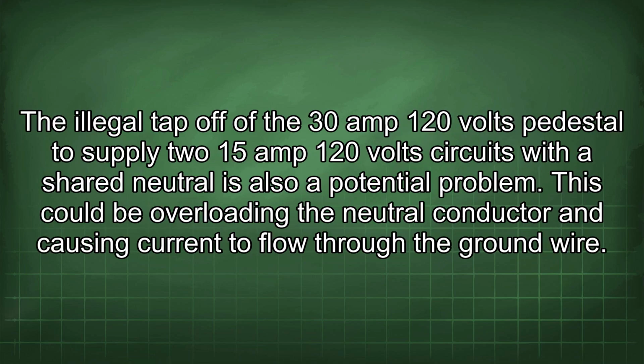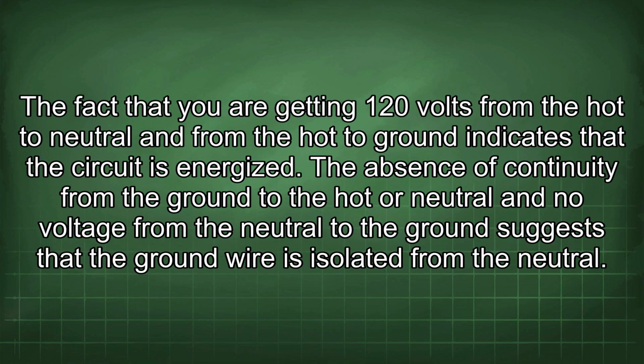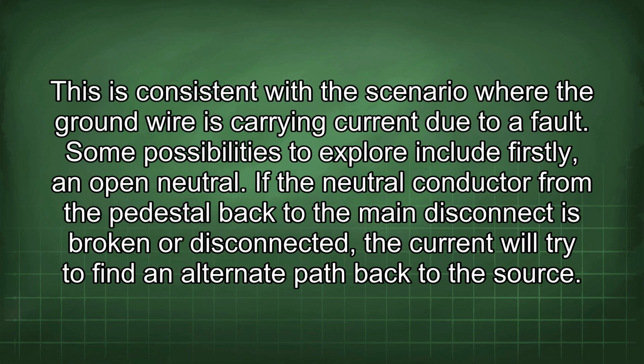The illegal tap-off of the 30 amp 120 volt pedestal to supply two 15 amp 120 volt circuits with a shared neutral is also a potential problem. This could be overloading the neutral conductor and causing current to flow through the ground wire. The fact that you are getting 120 volts from the hot to neutral and from the hot to ground indicates that the circuit is energized. The absence of continuity from the ground to the hot or neutral and no voltage from the neutral to the ground suggests that the ground wire is isolated from the neutral. This is consistent with the scenario where the ground wire is carrying current due to a fault.